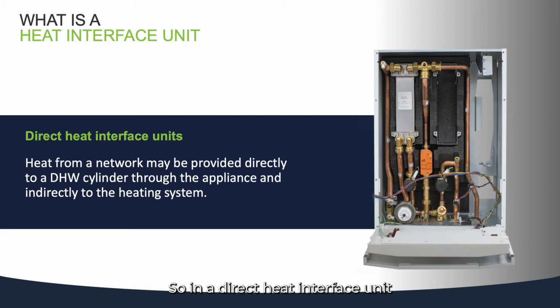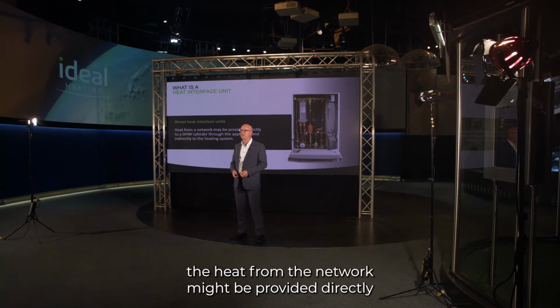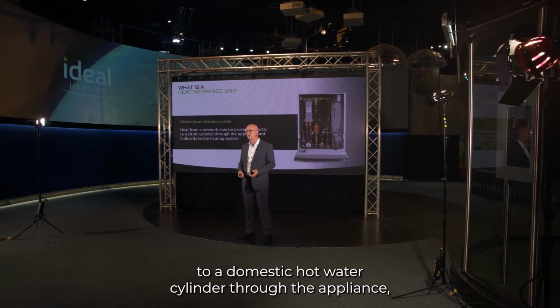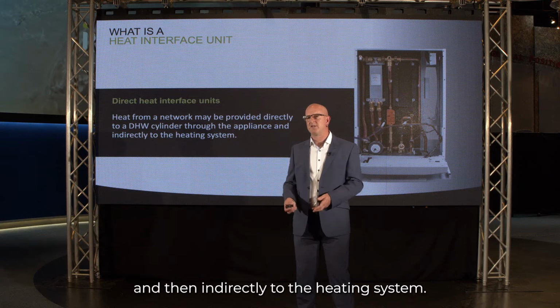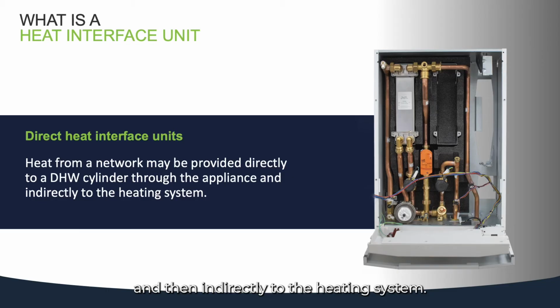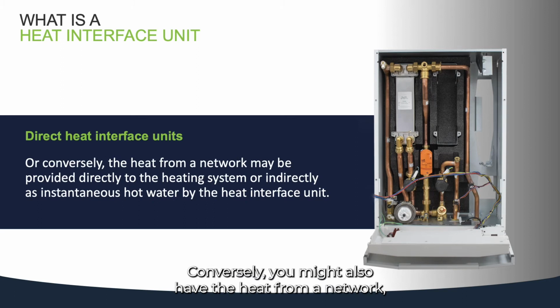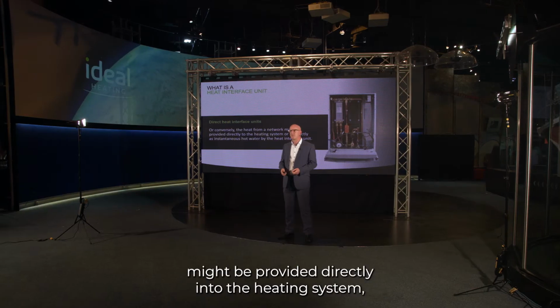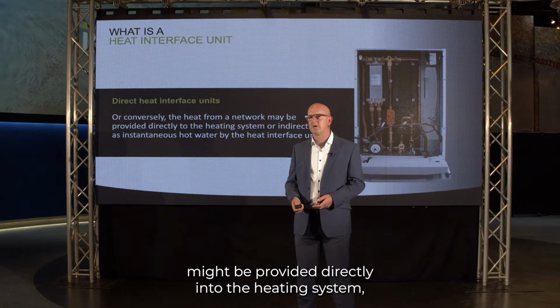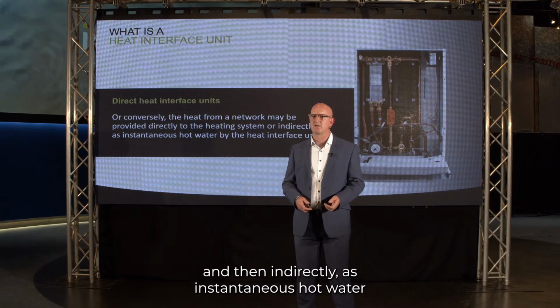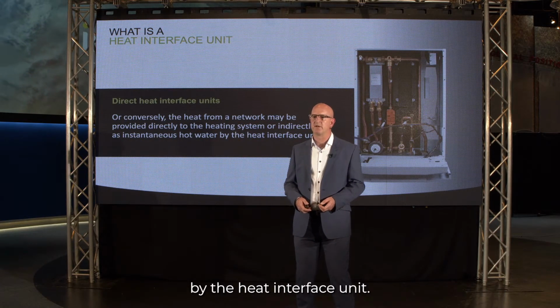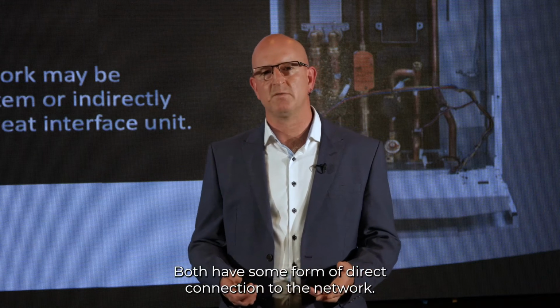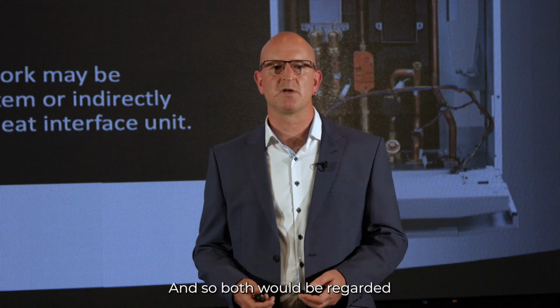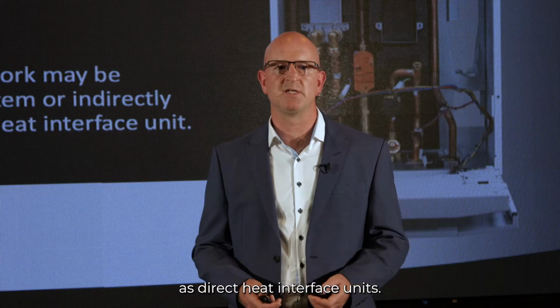So in a direct heat interface unit, the heat from a network might be provided directly to a domestic hot water cylinder through the appliance and then indirectly to the heating system. Conversely, you might also have the heat from a network provided directly into the heating system and then indirectly as instantaneous hot water by the heat interface unit. Both have some form of direct connection to the network, and so both would be regarded as direct heat interface units.